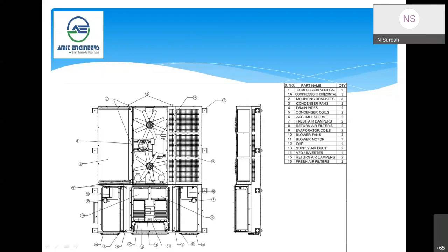Like, what is the purpose of the fresh air dampers? There are actuators available in this system. We'll cover what the function is, and the benefits from a safety perspective as well as functional benefits, in the coming slides. There are return air filters. In this return air filter, the dust particles will be filtered and the air passed on to the evaporator coil to bring down the temperature, and then it blows to the coach through the supply air duct.